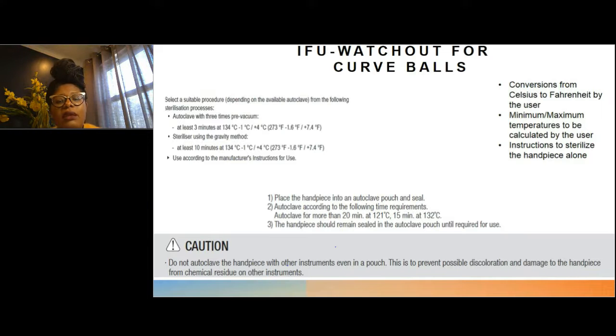So I say when you're reading the IFUs, it's important because you want to be able to develop a good program for the staff who are going to be reprocessing. Some IFUs, and here are some excerpts that I have placed here, you'll see that it will require the user to convert the temperatures from Celsius to Fahrenheit. There are also some that will require the user to observe maximum or minimum temperatures. It can be confusing to anyone who's reading that. There also is here an excerpt where the IFU says there are instructions for this particular handpiece: sterilize it alone. You can't put anything else inside of that sterilizer with that handpiece.